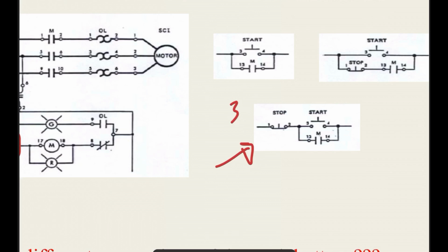Okay, now let's come to the third connection and ask questions for it. Will the motor start when the black push button is depressed? This is the black. Yes, it will start. Next question: will the motor stop when the red push button is depressed? This is the red, stop. When we depress it, does the motor stop? Yes, it stops. Explanation: when the red push button is depressed, the coil circuit of contactor M is interrupted, causing contactor M and its holding contacts to open, stopping the motor.